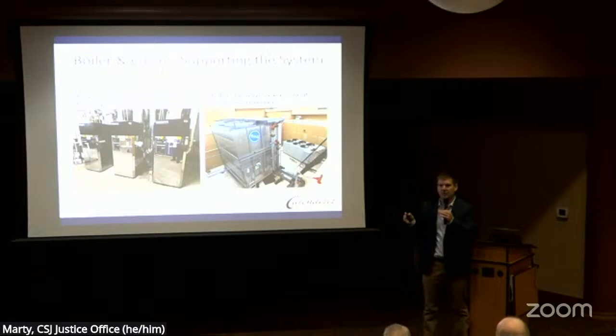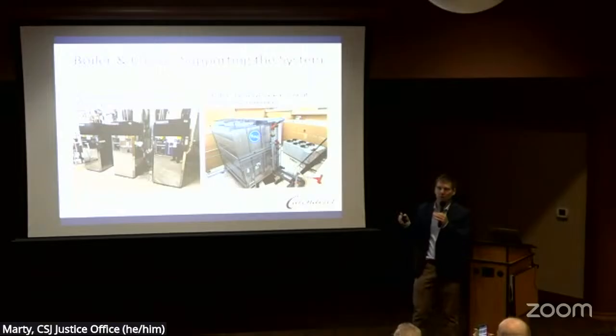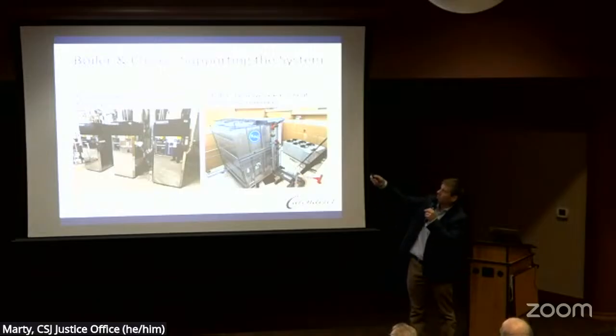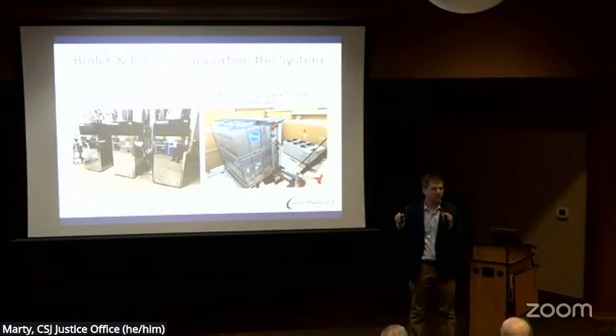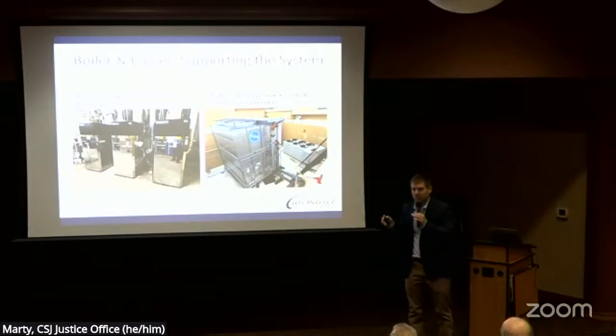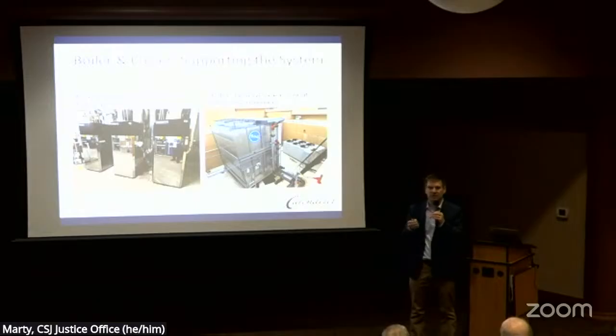What we're trying to maintain in the core loop — when I talk about the core loop, this is the water that is flowing through all of the piping out to the wells and back into the building. The system is designed to work between 40 degrees and 85 degrees. So we want that loop temperature to stay somewhere in between there. Now in wintertime, when the ground's getting cold, we're going to get below 40 degrees, so we need to supplement it somehow and get that temperature higher.